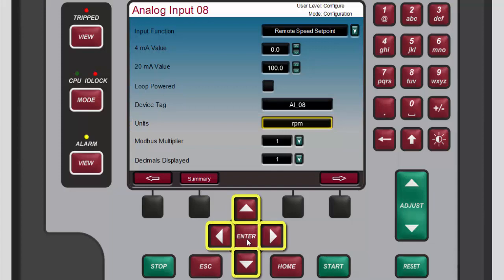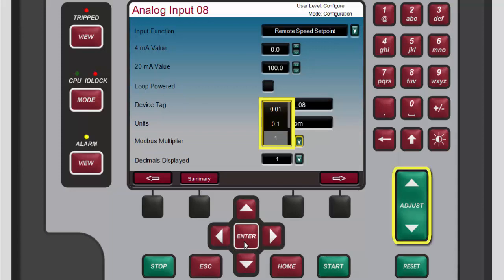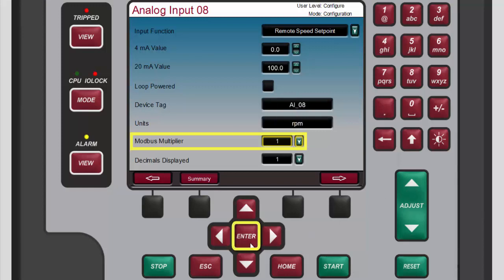Now use the navigation cross keys to highlight the Modbus multiplier box. This box allows you to select the multiplier to be used for the parameter address on the 505 slave Modbus communication link. For this demonstration we'll keep the multiplier as 1. To select a different multiplier, press enter to open the multiplier drop-down menu, use the adjust keys as many times as necessary to highlight the desired option, then press enter to select the highlighted option.